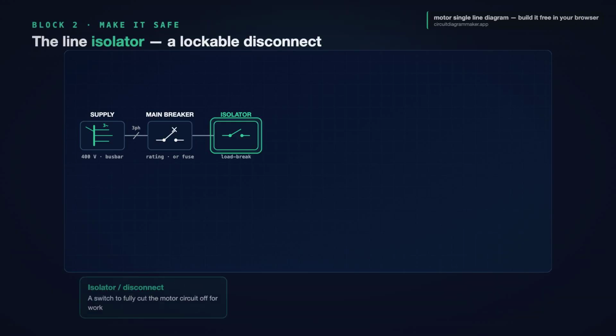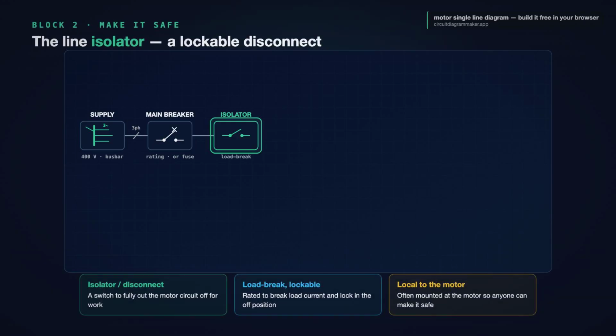Block 2, the line isolator, sometimes called the disconnect. This is a switch whose only job is to completely cut the motor circuit off, so anyone can work on it safely. On the diagram, it is a plain switch symbol on the line, rated to break the load current and to lock in the off position. The breaker protects, but the isolator makes safe, and they are not the same device. You will often see this isolator mounted local to the motor, so whoever is servicing it can kill the power right where they stand and padlock it there. Isolate to make safe. It belongs on every motor one line.